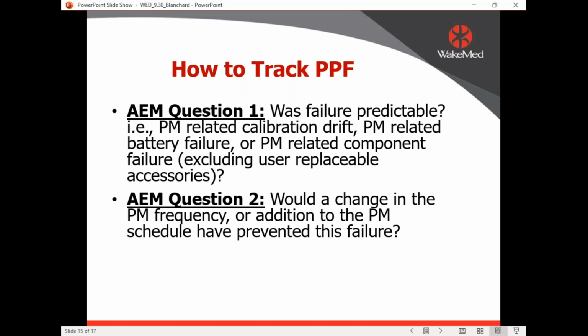Second question is, would a change in the PM frequency or addition to the PM schedule have prevented this failure? So if we had a device that we are doing a PM on, would a change in the frequency of the PM, if we shorten that window, have caught this failure? If that's how we determined our defib batteries, we're going to shrink the window down because I was getting a few yeses on this. Or in addition to the PM schedule, should we put that device on a PM schedule, even if the manufacturer says no PM? They're giving us the autonomy to make that decision, which I love. It's the whole right to repair.